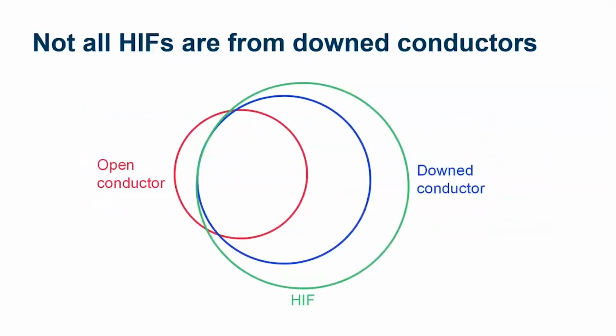Another thing to keep in mind when looking to apply AST is that we're detecting arcing faults, we're detecting high impedance faults on the system. Well, not all high impedance faults are necessarily a downed conductor. We can have a case where we have, say, a cracked or a dirty insulator, and we have arcing, a high impedance fault. AST will detect that. If we have, say, a tree branch that is brushing up against the line or making contact with the line when the wind blows in a certain direction, it's an intermittent high impedance fault, and we're going to detect that with AST as well. But if we're sending crews to look for a downed conductor on that line, they may not see anything. So it's important to understand how this technology works in order to understand how best to apply it.